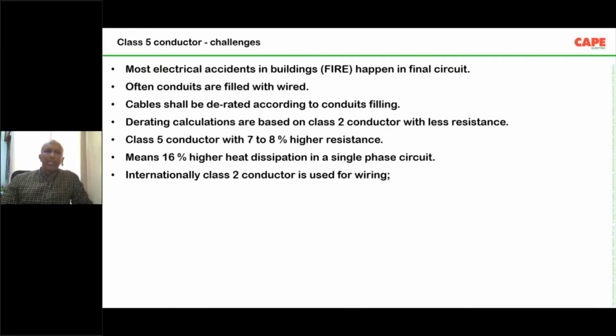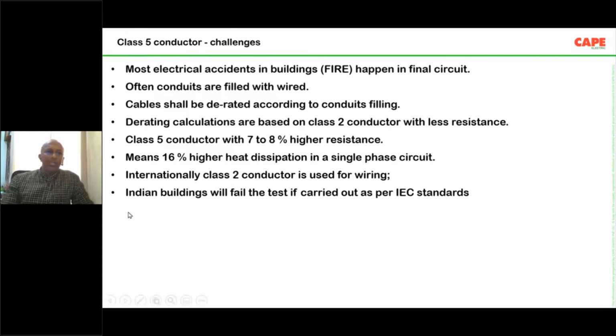Internationally, class 2 conductors are used for wiring. Indian buildings will fail if the test is carried out as per the IEC standard. What I wanted to mention here is that Indian buildings will fail if the test is made as per IEC standard. If somebody, maybe an international company, says, I am coming from the UK, I want my Indian building to be equal to my building in London, and they try to test the Indian building, you can be sure that the building will fail.